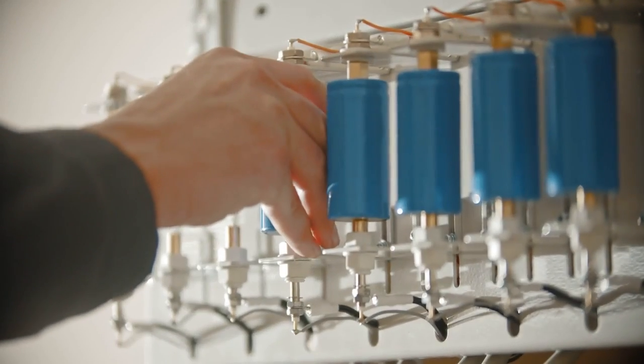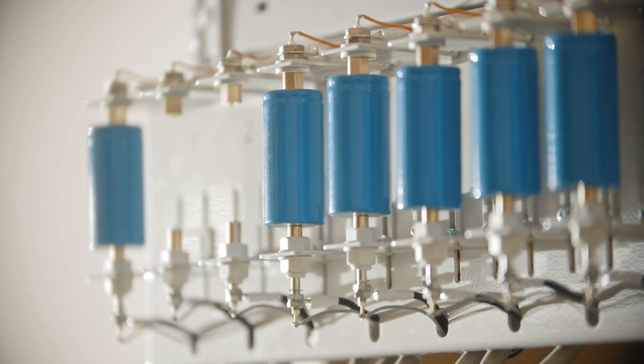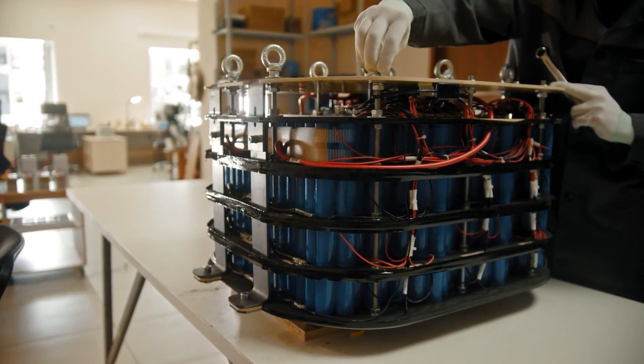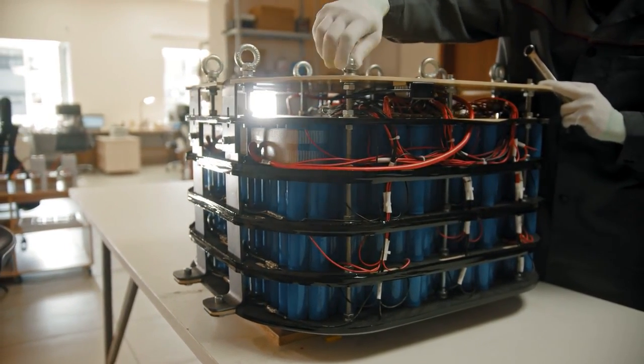The price point is very, very low. And lithium-ion, while it works beautifully in small format, if you start putting hundreds of thousands of lithium-ion batteries in close proximity, you have to be very aggressive about thermal management because they heat up. If they heat up, they could go supercritical and burst into flame. In terms of round-trip efficiency, safety, and long service lifetime, I think the liquid metal battery is a better fit for grid-level storage.